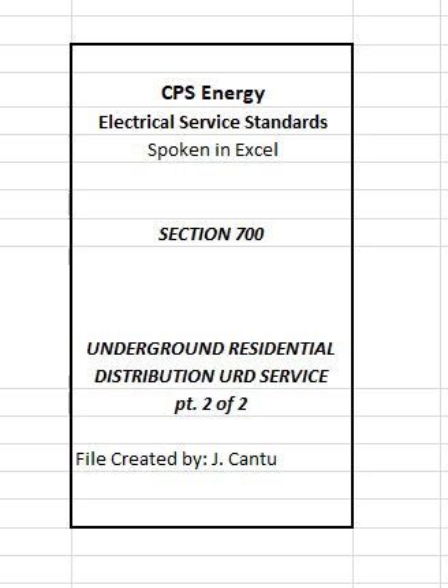707 Metering. All metering equipment shall be installed on the exterior of buildings or structures in accordance with Section 1800. Customer shall provide CPS Energy an approved space on the building wall or structure for metering equipment. Customer shall furnish and install single-phase, self-contained meter sockets for single-phase 120/240 volt services provided on residences, refer to Figure 1801. Note: service equipment for residential services shall be located at the same location as the metering equipment in accordance with Section 400. See the following figures in the specification manual.